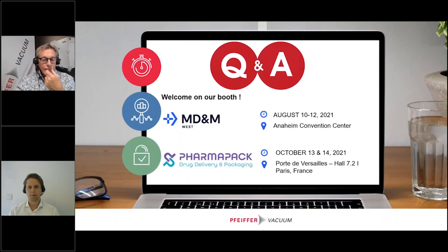Maybe one more question. Does Pfeiffer Vacuum support documentation and qualification of an instrument or process? What we propose together with our equipment is a complete package, including IQ and OQ documentation with a factory acceptance test and site acceptance test, of course, on the customer side. Pfeiffer will also support you during the PQ, to answer your questions and help you during the process qualification you will perform if you decide to use our technology.